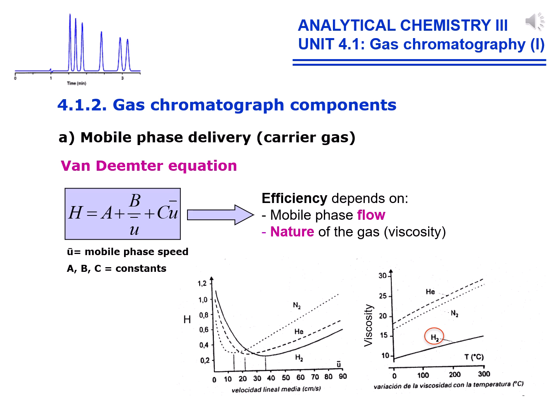The velocity of the mobile phase also depends on the nature of the gas, mainly its viscosity. Thus, hydrogen is, of the three commonly employed gases, the one that allows faster separations under equal conditions, by giving more flexibility in terms of flow rate. It should be noted that the viscosity of these gases increases with temperature, so this is another important parameter for increasing efficiency. For example, at the same temperature, helium is more viscous than hydrogen, so it's more convenient to work with hydrogen if possible.